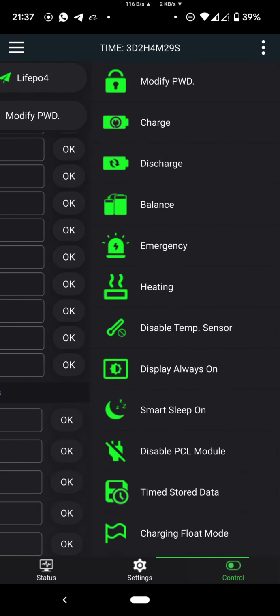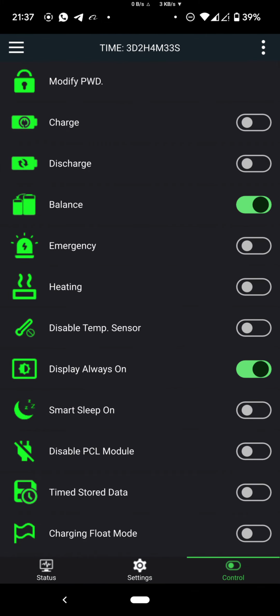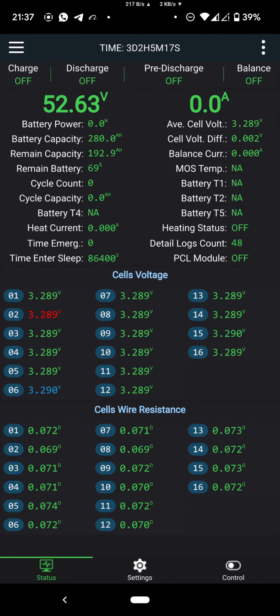Okay, now on the last tab, we can see we can modify the password. I would recommend you change the password as soon as possible. Default password is 126. There's the charge switch, discharge switch, balancing switch, emergency switch, heating, disable temperature sensor. If for some reason you need to disable the temperature sensor, keep in mind with this BMS the temperature sensors cannot be removed since they are included with the sensing wire harnesses. But if you disable them, you won't get any readings on the status page. So it will totally disable them. I requested from JK to keep the values, but just ignore them.